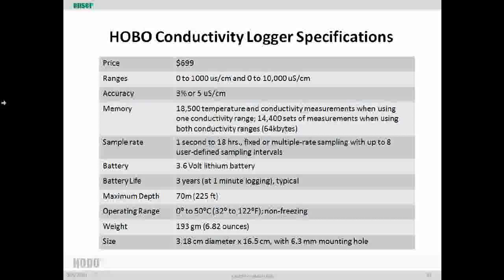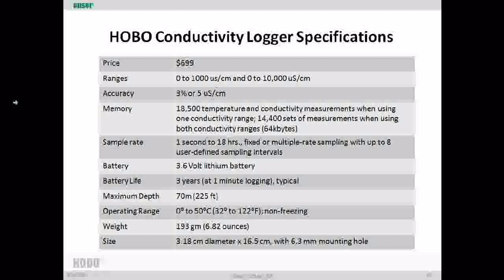And the accuracy is 3% or 5 microsiemens per centimeter, whichever is larger. So if you're down in the very low conductivity range, let's say in a glacial runoff stream, below 100 microsiemens per centimeter, then the 5 microsiemens per centimeter spec is going to be what applies. For larger conductivity measurements, that 3% spec is what's going to apply.